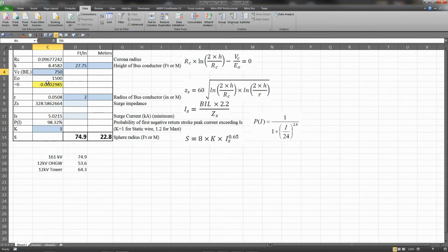Now, at 110 kV, we actually run into a limitation. According to IEEE 998, they suggest that you limit this number to 2 or 3 kA. And here I've limited to 3, so any value below about 69 kV will give us a minimum of 3 kA, which says that we have a 99.55% chance of it being 3 kA or greater. So that's what we're looking for. This is a minimum value. So we have a 0.45 chance of it being less than this and actually running into a problem.